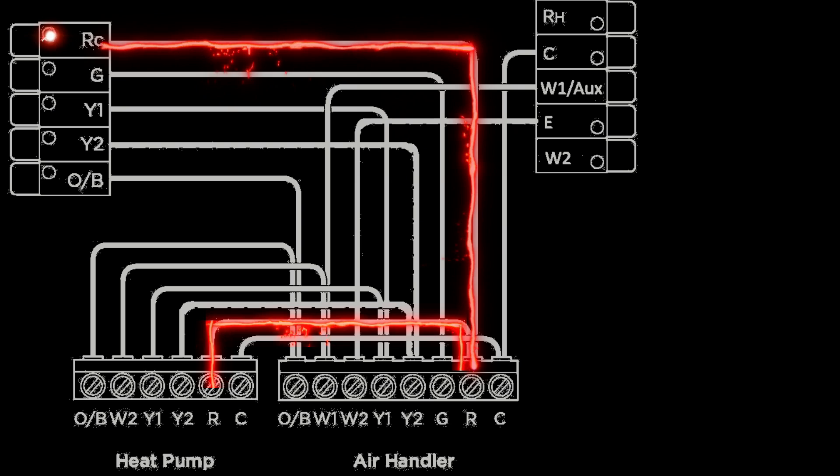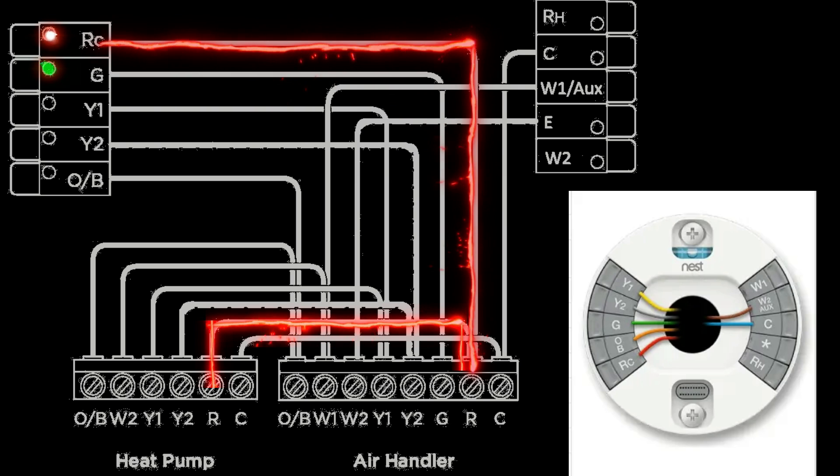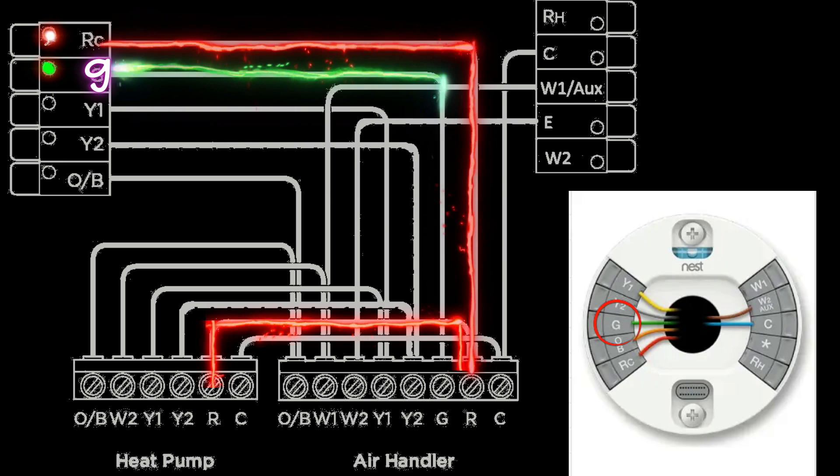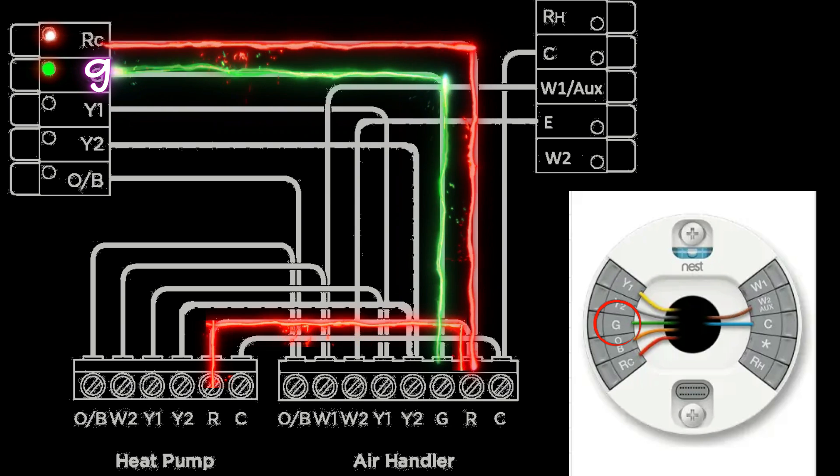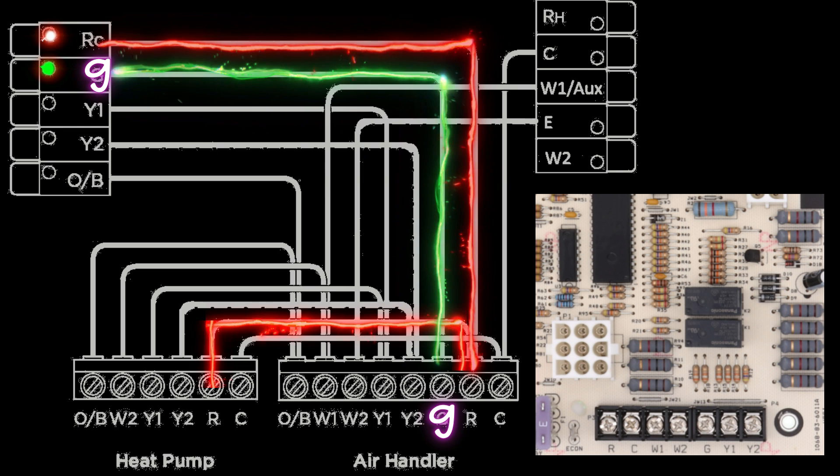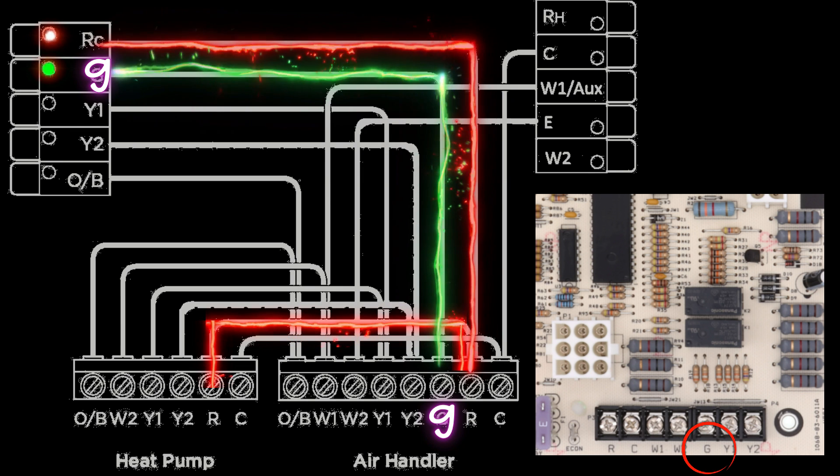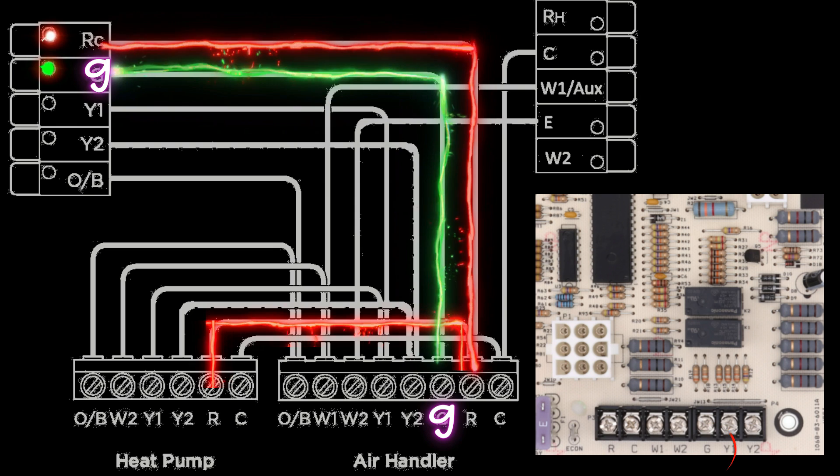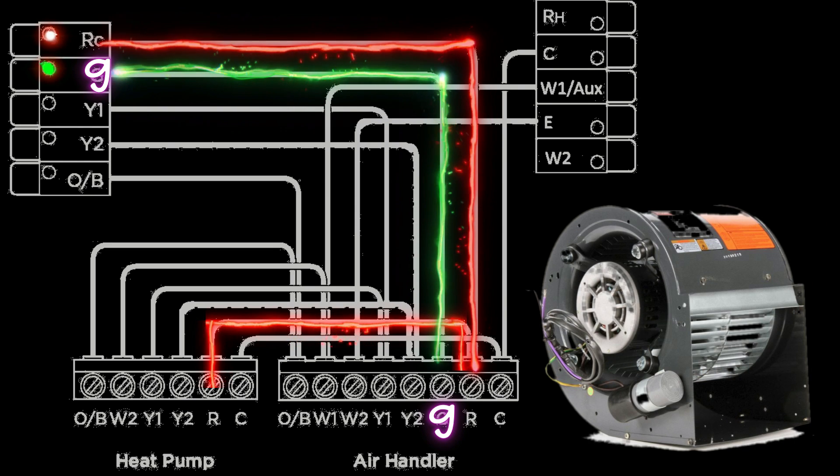Now the first thing the thermostat is going to do is take power from that RC terminal and power the G terminal. And you're going to have a green wire from the G terminal on your thermostat going up to the G terminal on the control board in the air handler. Now the whole purpose of this wire is to activate the blower motor.